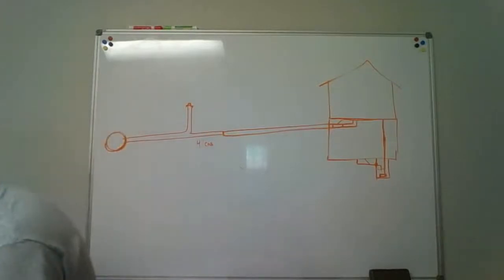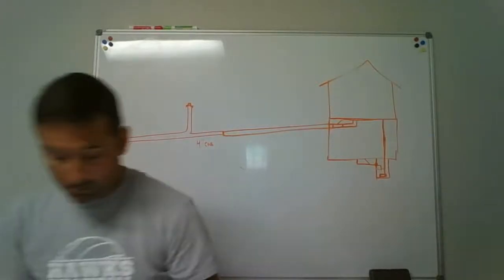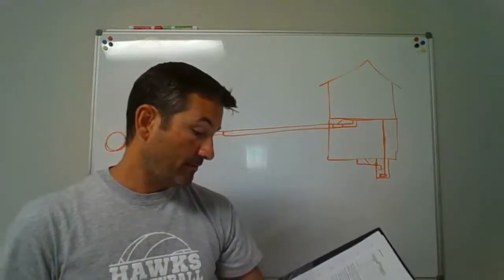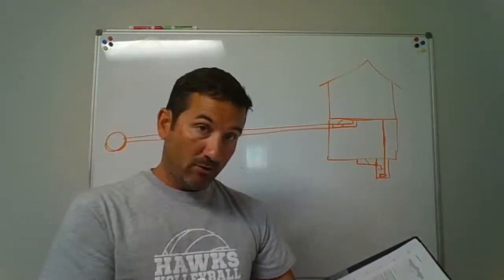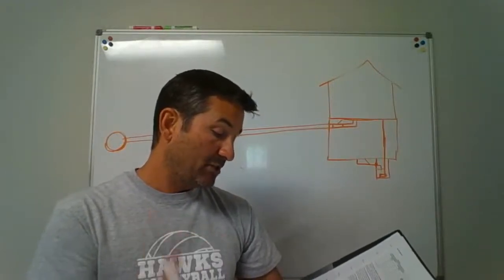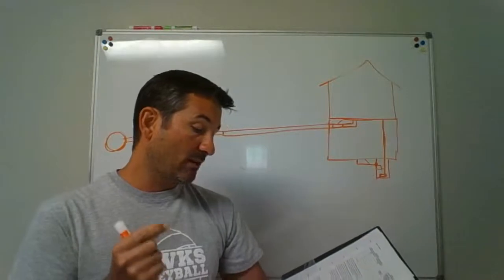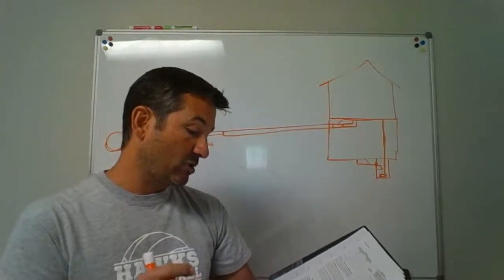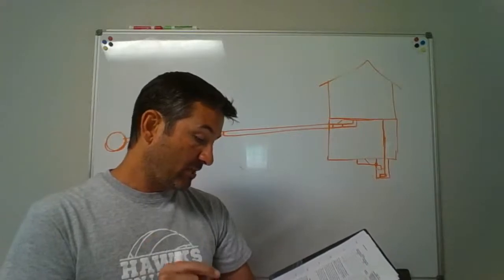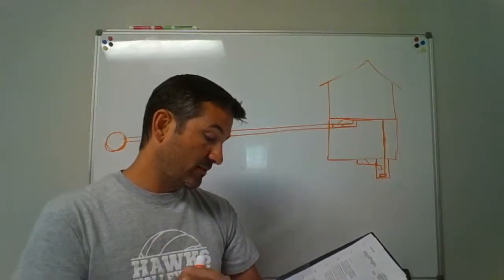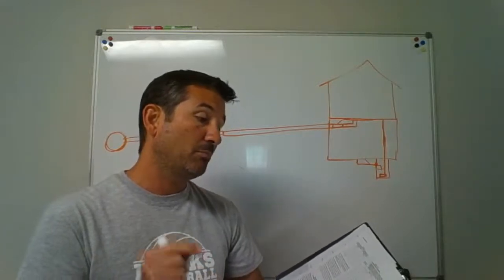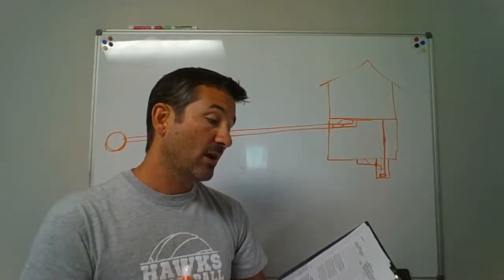That you catch. Now, what it's saying is what's required on it. What kind of valves are required? A check valve, there's one, a full open valve, and a means for clean out located on the discharge side of the check valve. It should be installed in the pump or ejector discharge piping between the pump or ejector and the gravity drainage system.